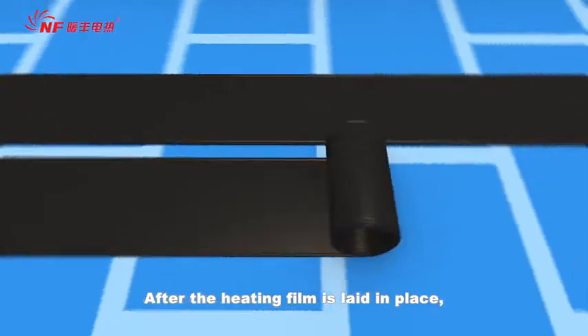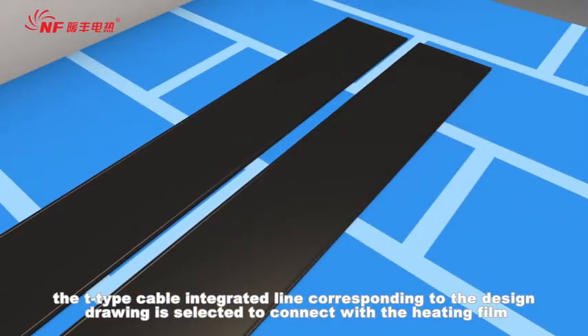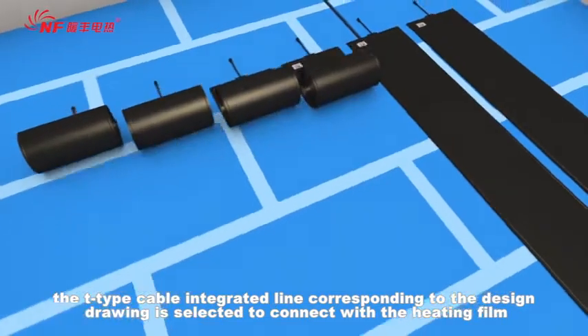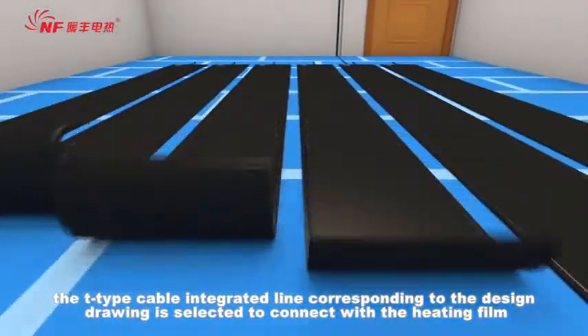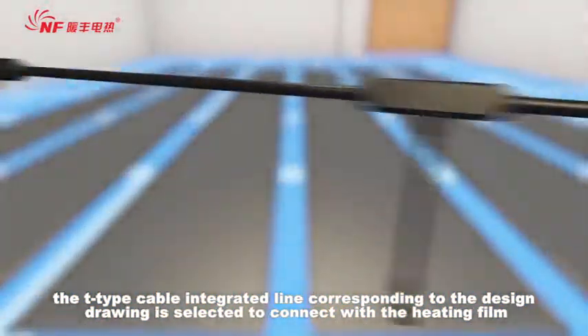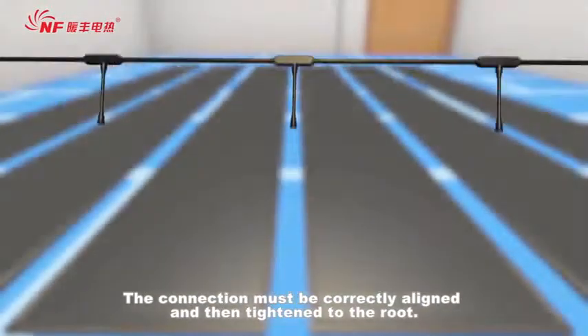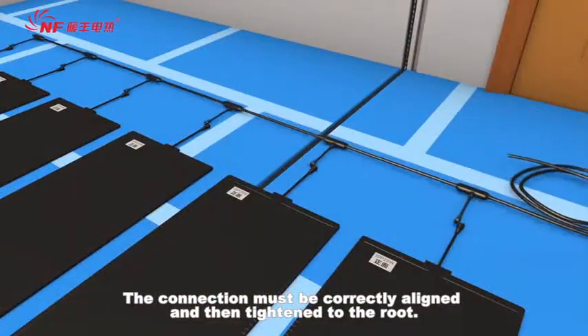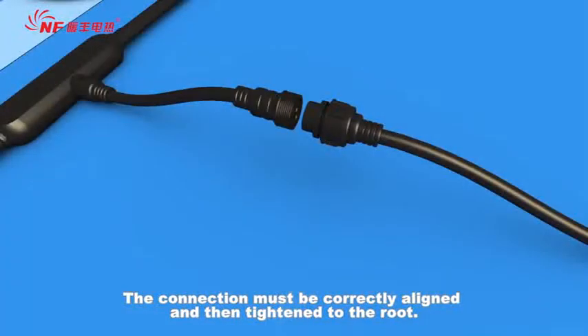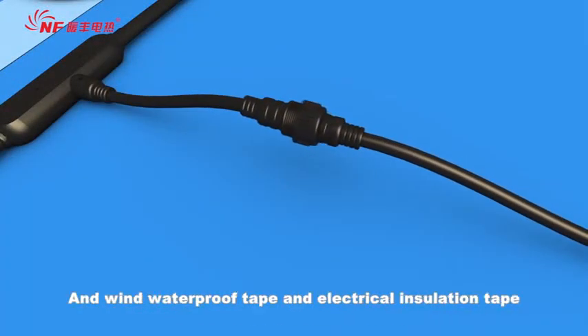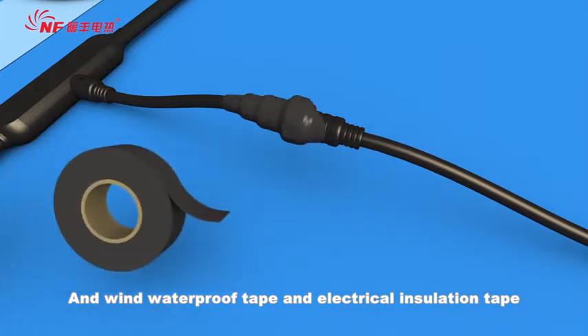After the heating film is laid in place, the T-type cable integrated line corresponding to the design drawing is selected to connect with the heating film. The connection must be correctly aligned and then tightened to the root. And wind waterproof tape and electrical insulation tape.